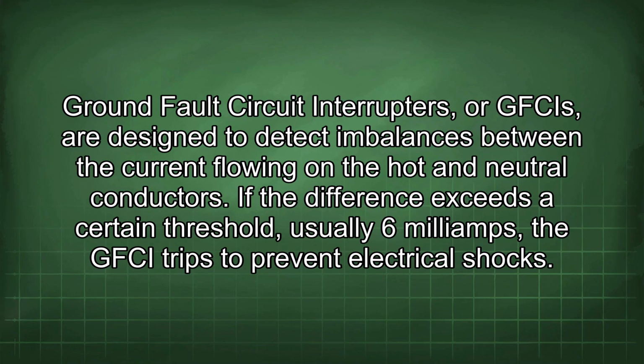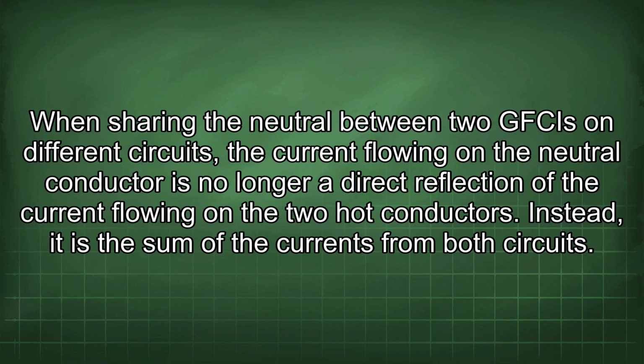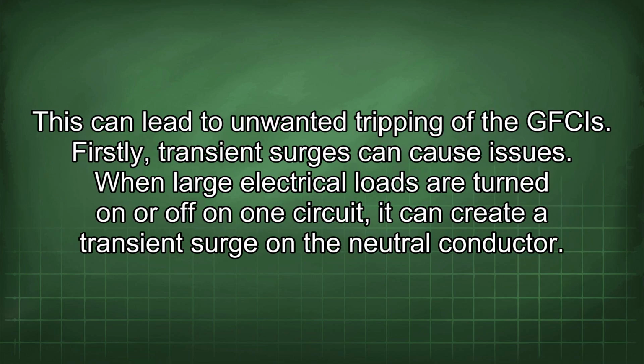Ground fault circuit interrupters, or GFCIs, are designed to detect imbalances between the current flowing on the hot and neutral conductors. If the difference exceeds a certain threshold, usually 6 mA, the GFCI trips to prevent electrical shocks. When sharing the neutral between two GFCIs on different circuits, the current flowing on the neutral conductor is no longer a direct reflection of the current flowing on the two hot conductors. Instead, it is the sum of the currents from both circuits. This can lead to unwanted tripping of the GFCIs.